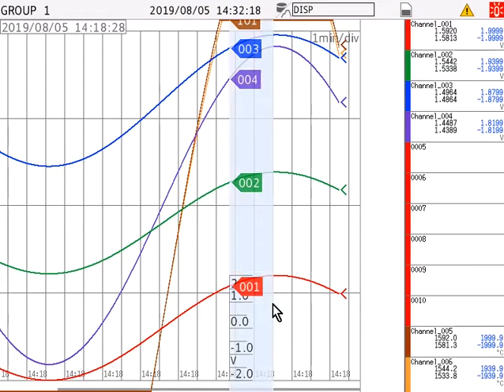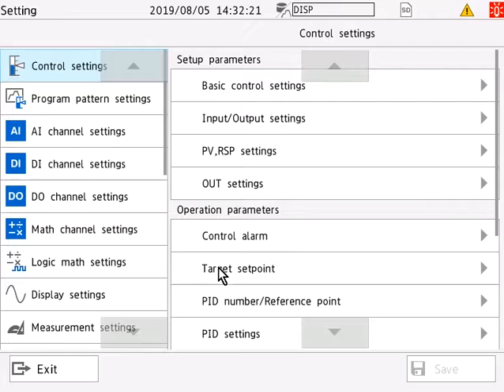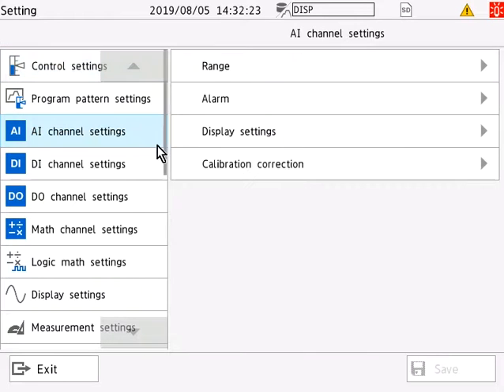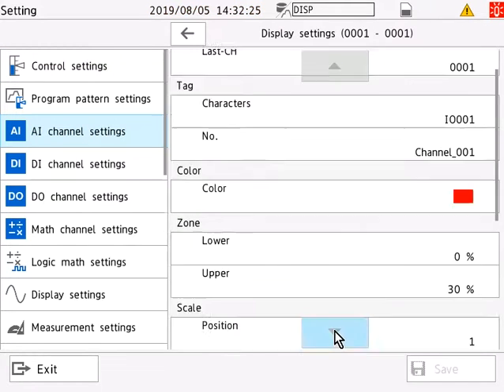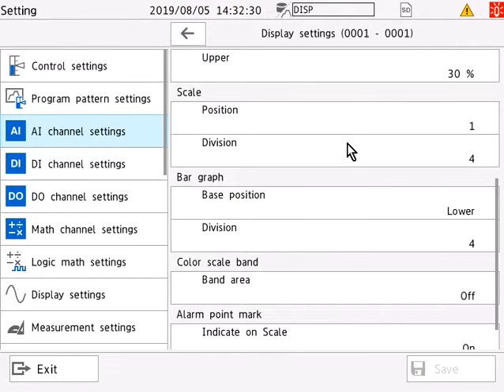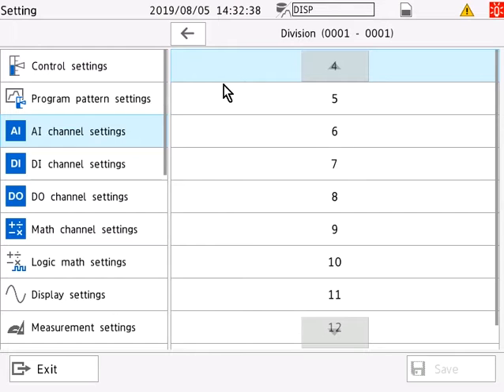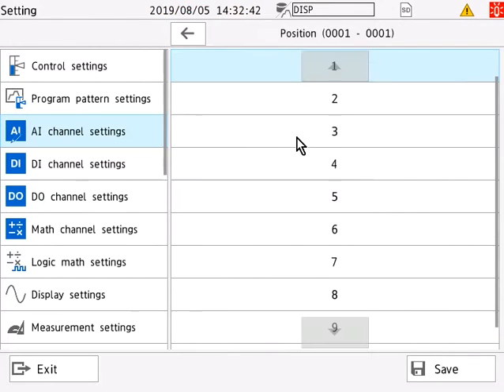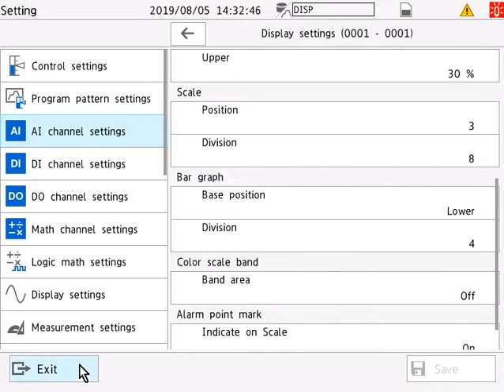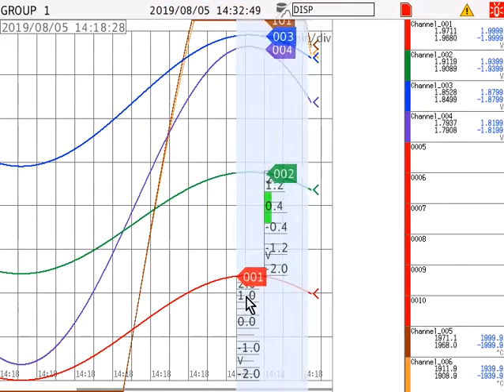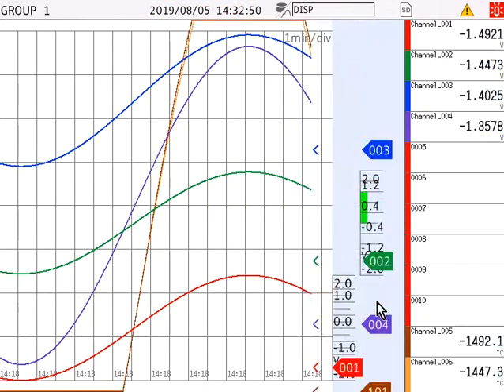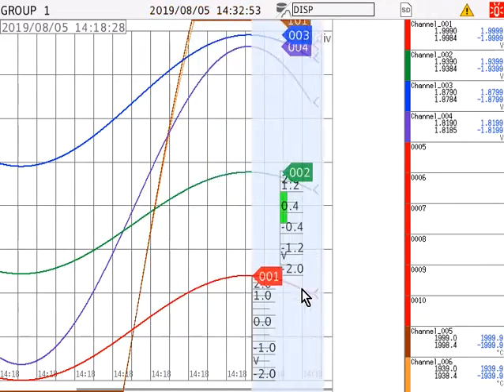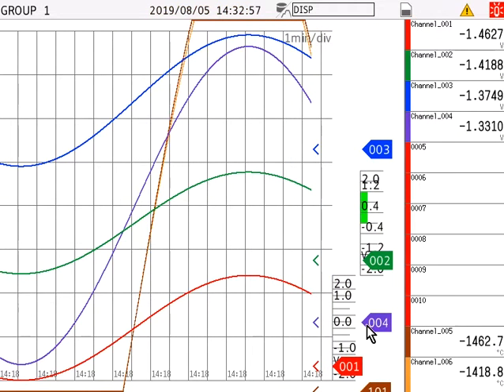So your scale will be able to give you the range of measurement and you can set the scale positions when you want to display one or more scales on the trend display. You can also use the division option to set the number of divisions you want to make within the main scale mark. So if we select 8 scale marks, save and head on back, you'll notice that we have multiple scales that are each divided into 8 separate divisions.